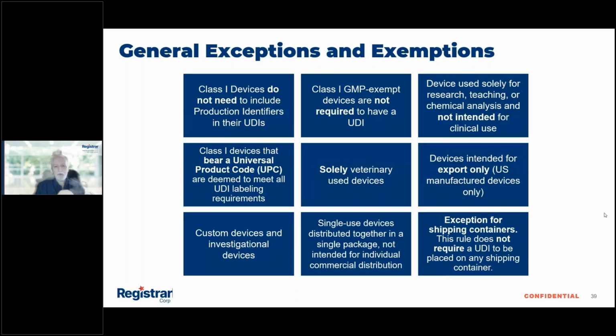Then we have solely veterinary used devices. You don't need UDI or GUDID requirements. You are good to go. There is no requirement for veterinary devices only. If you have a device that you are marketing and labeling for human and veterinary use, yes, you have to comply with the GUDID and also the UDI regulations. Devices intended for export only, that applies only to US manufacturers. So if you export the device and it's not for the US market in any way, then you don't have to comply with UDI and GUDID.